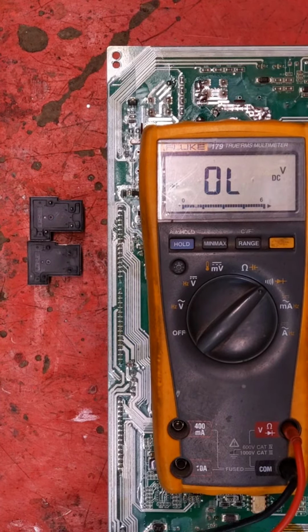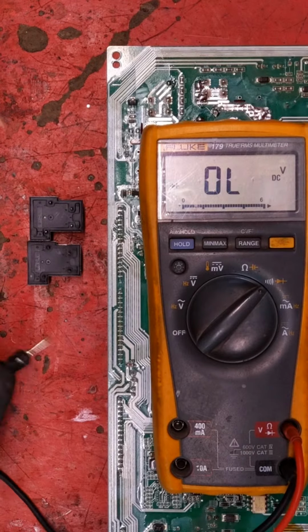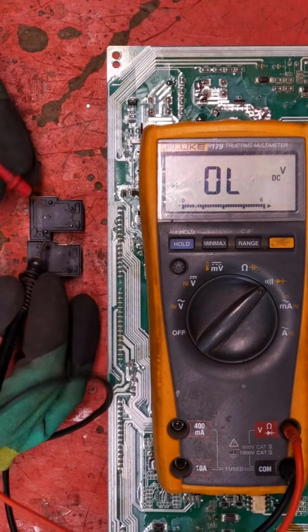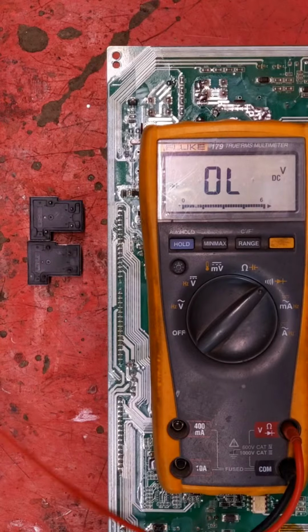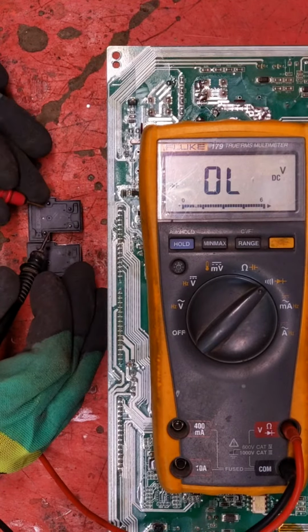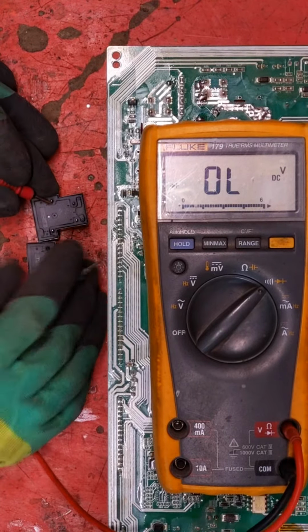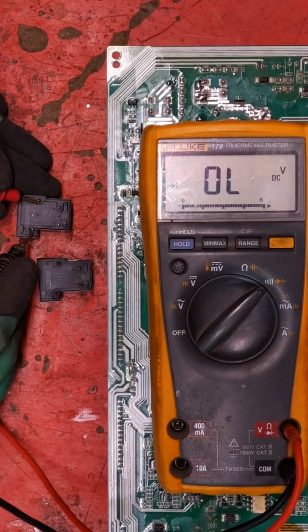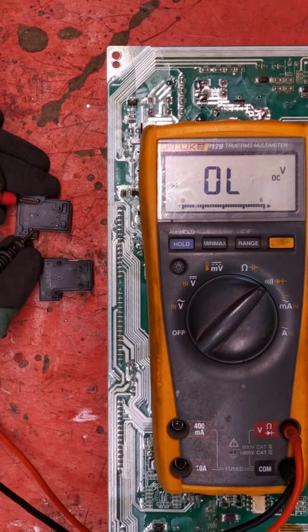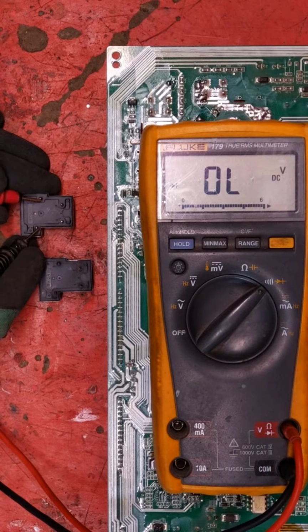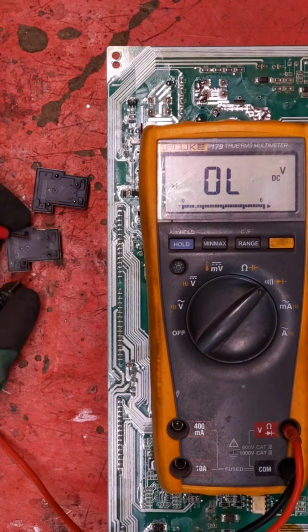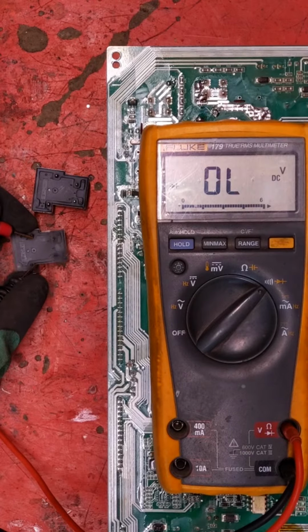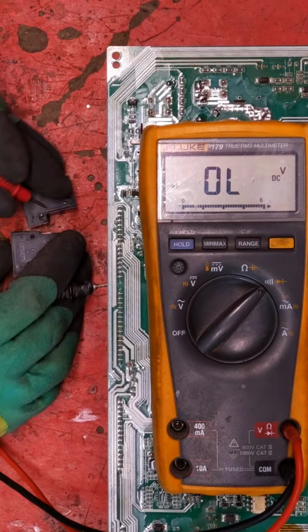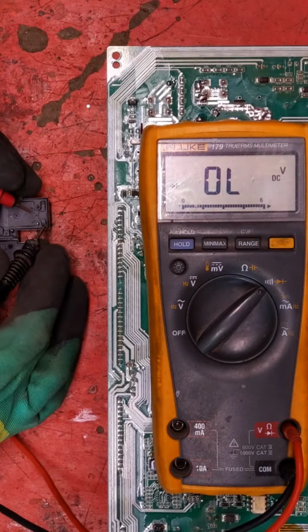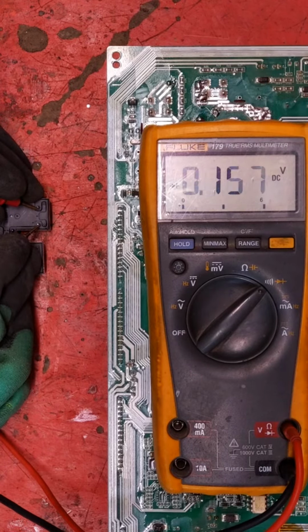First we need to check the common pin with the normally open pin. In this condition we don't need any continuity, because this is the normally open pin, so here we have no continuity. That means it's okay. After that we need to check the relay coil resistance.